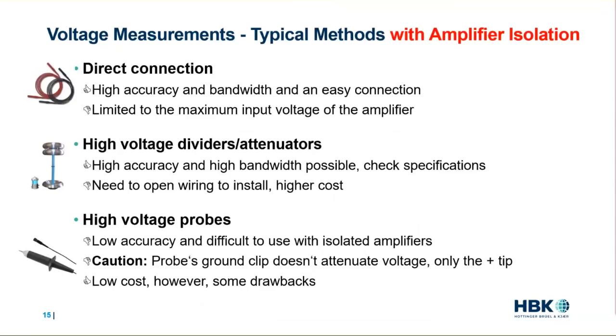Now, here's a list of some of the typical methods used to connect high voltages to measurement amplifiers with isolation. If the amplifier does not include isolation, then you're going to need to add an additional system, an isolation system, in front of the amplifier. Now, the ideal and easiest high voltage connection, of course, is the direct connection for maximum accuracy and bandwidth. However, this is only possible when the voltage is within the input range of the amplifier.